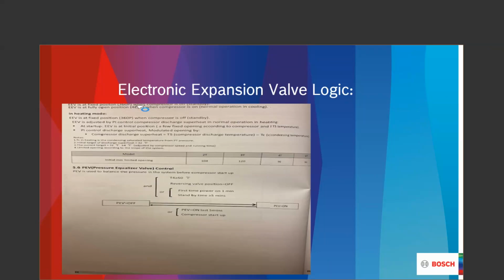And guys, we have not had any major problems with E-valves. We've not had a whole lot of problems with TXV valves. The issue is installers not dehydrating the refrigerant lines. So we've got to be very, very careful about the process. When the book says pull that thing down into a micron vacuum, we need to pull it down into a micron vacuum. It is no longer a purge type situation that we may have seen 25, 30 years ago with the R22 and capillary tubes and accumulators and things like that. So a very deep vacuum, a triple vacuum, is great to dehydrate those refrigerant lines.